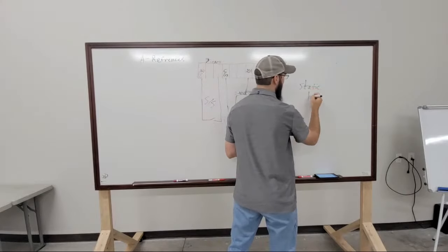You also need to input the amps, horsepower, Hertz, RPM, volts, and power factor. Most of the time you'll never have to mess with the power factor, but on certain applications and older drives, that is a very important number because the drive is not going to control the motor properly if it doesn't have the power factor calculated correctly. It's usually something like 0.9. The vast majority of your heavy commercial applications are going to be asynchronous motors — that's going to be your commissioning value.